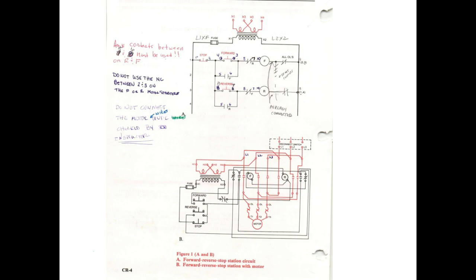This is the wiring diagram. Normally we don't use the wiring diagram to wire the control circuit. Look how complicated this thing starts to get. What we normally use the wiring diagram for is to wire the power circuit. Here's the power circuit right here. It shows I bring L1, L2, and L3.